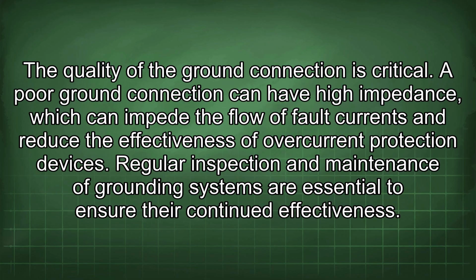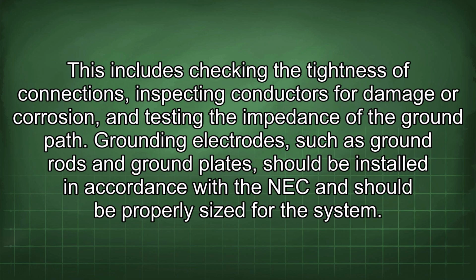A poor ground connection can have high impedance, which can impede the flow of fault currents and reduce the effectiveness of overcurrent protection devices. Regular inspection and maintenance of grounding systems are essential to ensure their continued effectiveness. This includes checking the tightness of connections, inspecting conductors for damage or corrosion, and testing the impedance of the ground path.